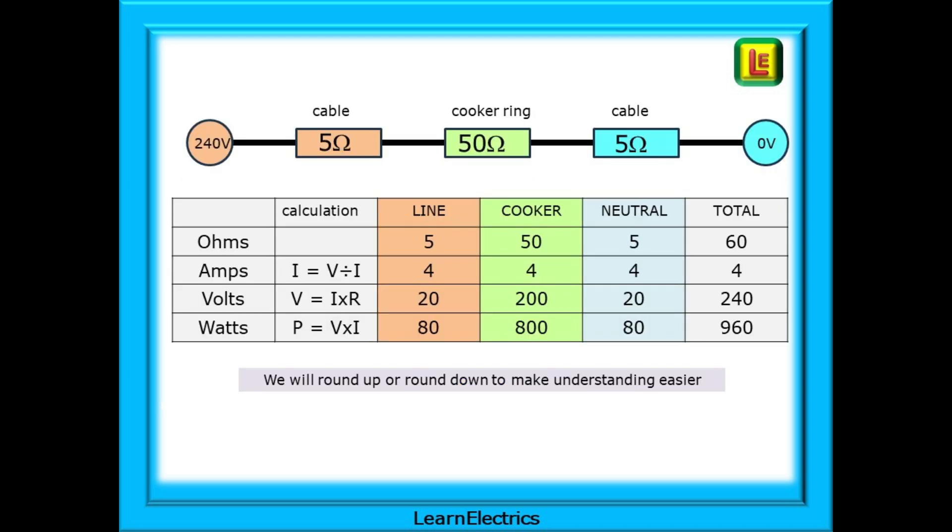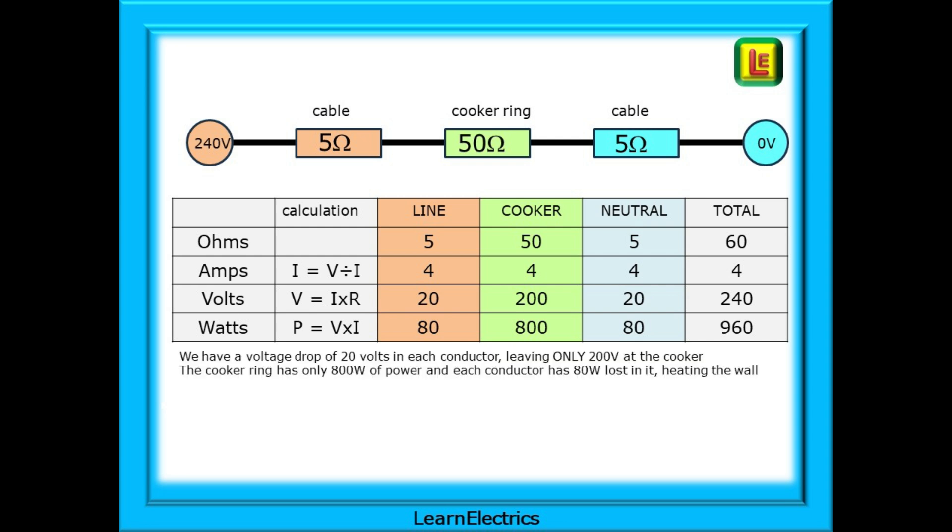This table shows the calculations that we've made. The current flowing through each part is the same at 4 amps, and we can now work out the voltage drop in the cables and across the cooker. Each conductor has a volts drop of 20 volts, 40 volts in total, leaving just 200 volts available at the cooker. This means that the cooker ring can only produce 800 watts of power, with 80 watts lost in each of the cables, just heating up the walls. The customer is paying for 960 watts of energy, but only actually getting 800 watts of useful power.